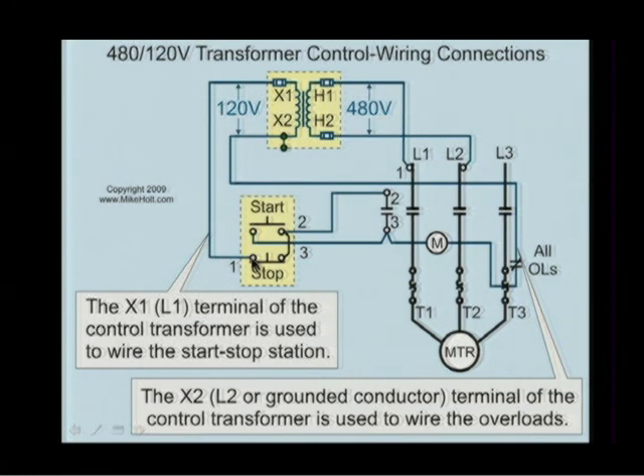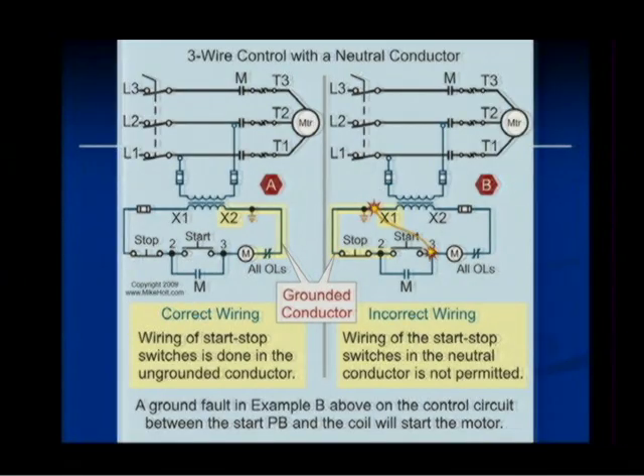Right? So whether it's 480 to 120, it's not that big of a deal. It's still the same basic 3-wire control circuit. All right, 3-wire control circuit with a neutral. Well, it's 120 volts, so it is a neutral. Using that example, again, we'll have this already color coded, so they're all black, all by whatever's pre-wired. And the neutral conductor comes off of L2, which is connected to the coil.